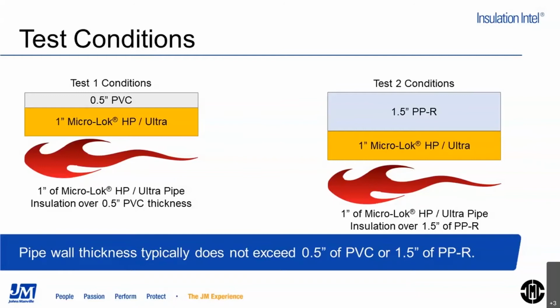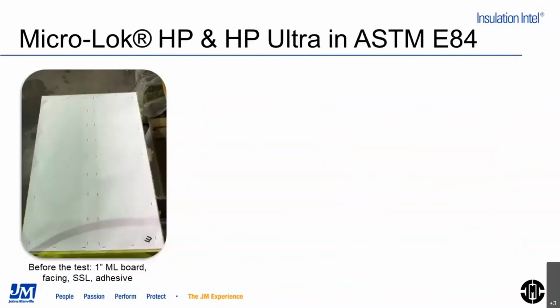And why do we go with the thicker as opposed to thinner? Because both materials are combustible. By using the thicker material, we're technically testing the worst case scenario because that's the most fuel for the fire. So again, that was the reason we went with the thicker boards for this testing. Now let's look at the pictures and get a little closer to the test. Less theory, more practice here.